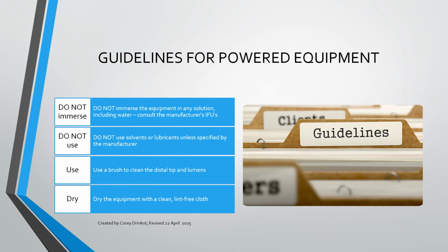The guidelines. Just remember with these hoses and these hand pieces, the attachments themselves are fine, but mainly with the hoses and the hand pieces, most of the time you cannot submerge these at all. We do not want water or the water solution to get into these components. If water gets in there, they're not going to work right, which means we have to send them out for repair, which means it costs the department money. We do not use anything that is not required for us to use according to the manufacturer IFU. Some hand pieces and some components with them need to have lubrication. Some do not. So we have to follow that IFU.